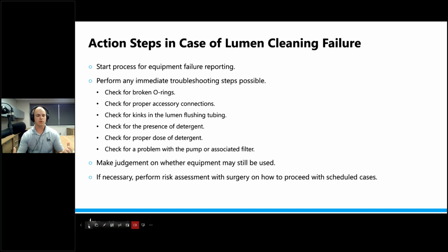And I already mentioned, make judgments on whether that equipment can still be used. And I used real world examples for that. And if necessary, perform a risk assessment with surgery on how to proceed with scheduled cases. I told you there's many places out there that only have one ultrasonic or one washer disinfector or what have you. You've got to look at your IFUs. If they don't have built into the IFU a manual process that you can do in lieu of having automated equipment working and functioning, then you really need to start considering how we are going to process these instruments. Do we have to send them to a neighboring facility within the system? Do we have to shut it down and maybe come up with another idea? Do we have to go as far as rescheduling? These are all things that we should be asking ourselves and discussing with upper level management, including the operating room.